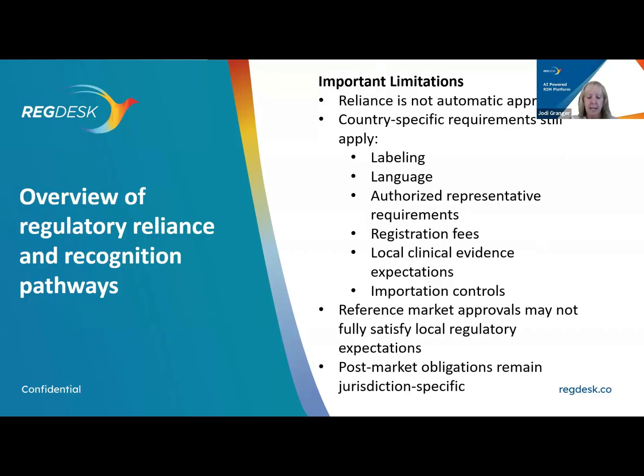There are important limitations that you should be aware of when you're creating your global regulatory strategy and factoring in the reliance models. Reliance is never equivalent to an automatic approval. Each jurisdiction still maintains country-specific requirements. These are often including local labeling obligations or content. Certainly, language requirements will be factored in. There are authorized representative rules. There will certainly still be registration fees associated with each country. There may be local clinical evidence expectations. There are some countries that require you to demonstrate that your clinical data is representative of the patient population within their jurisdiction. And of course, there are also importation controls that will vary from one jurisdiction to another.